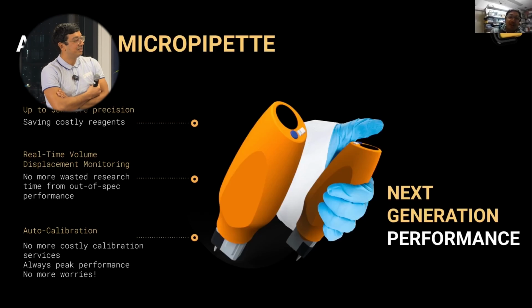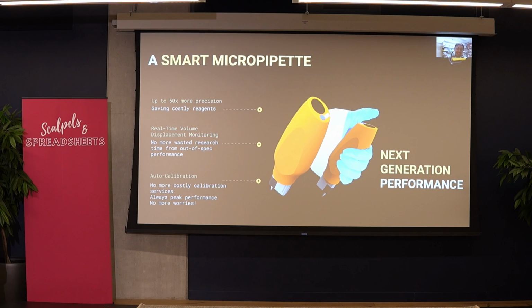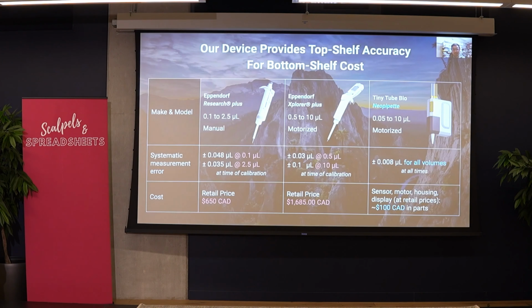So we made a new sensor that can measure microliters way more precisely. Our sensor can do 50 times more precision than current devices. The sensor is self-monitoring, so in real time the device knows how much volume is being displaced, and if there's something wrong with the internal mechanism or something's off, it will alert you. And the sensor calibrates itself, so you don't need to pay for costly calibration or ever worry that your pipette is not performing well ever again.